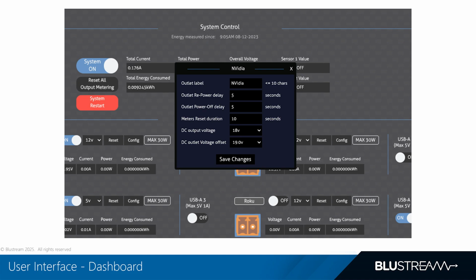For the low voltage model, you'll also choose a DC voltage per outlet, available through presets which cover common AV needs, and you can fine tune that with a plus 1 volt offset. In the example shown, the NVIDIA Shield Pro calls for 19 volts, so here we select 18 volts and apply a plus 1 volt offset to hit exactly 19 volts. That means no external brick is required.